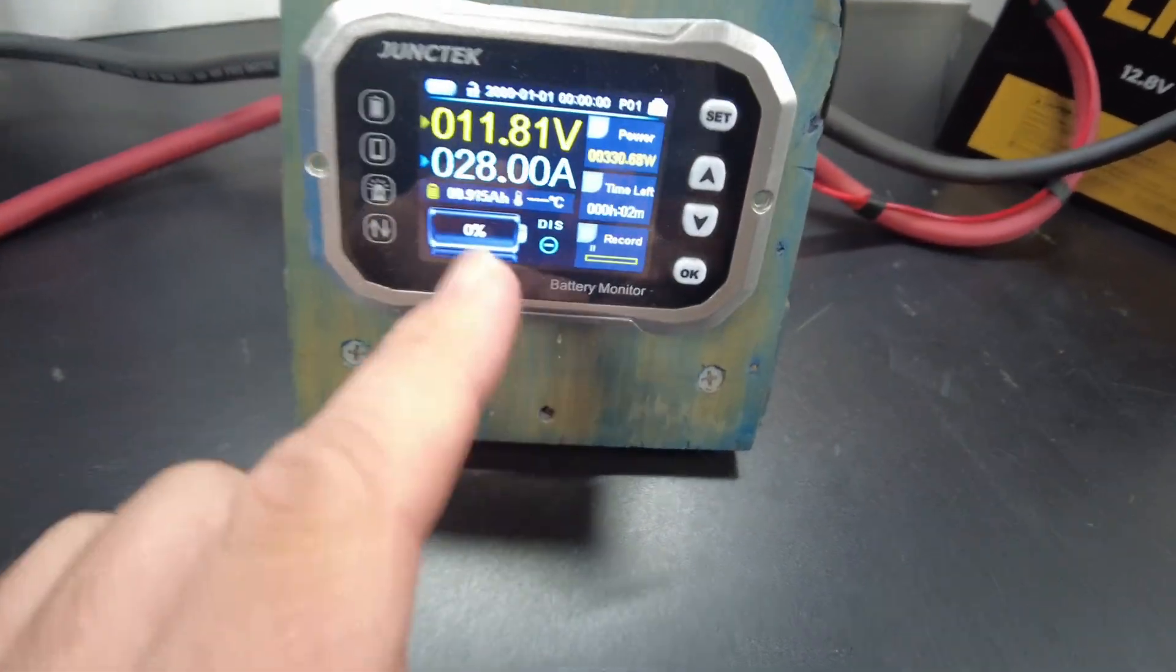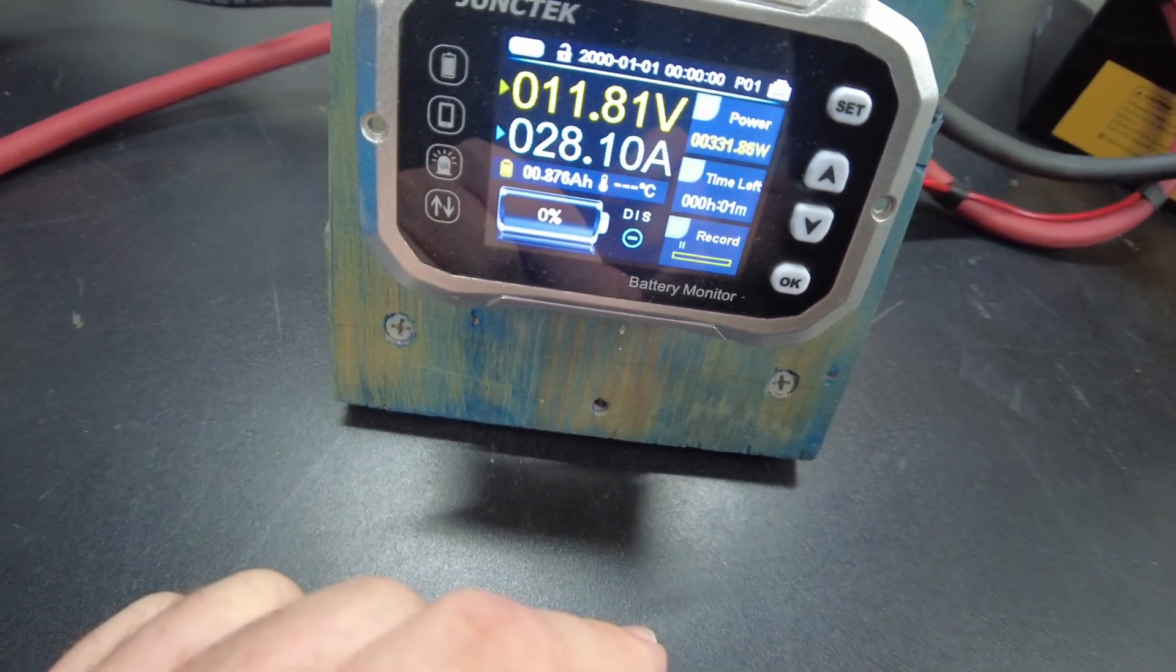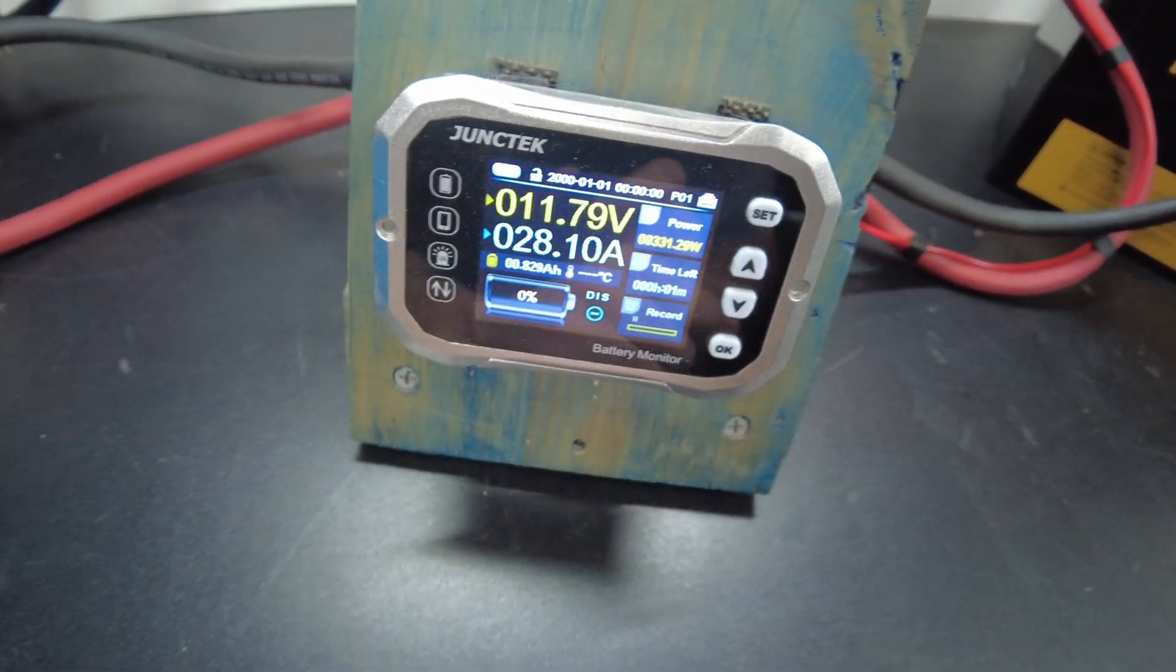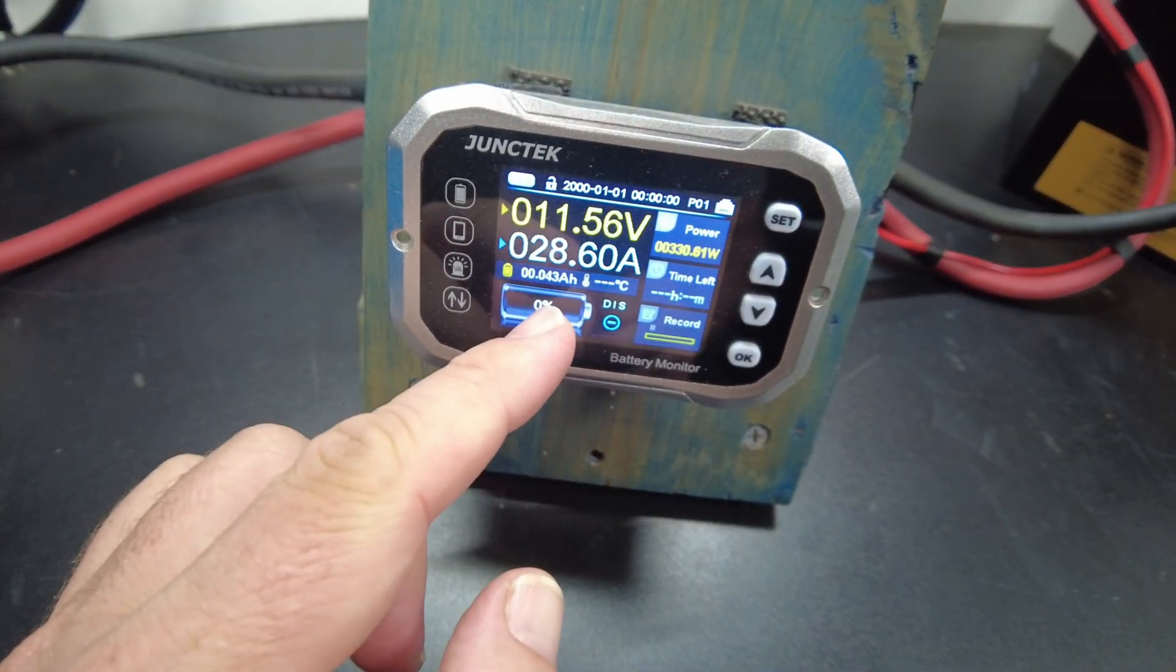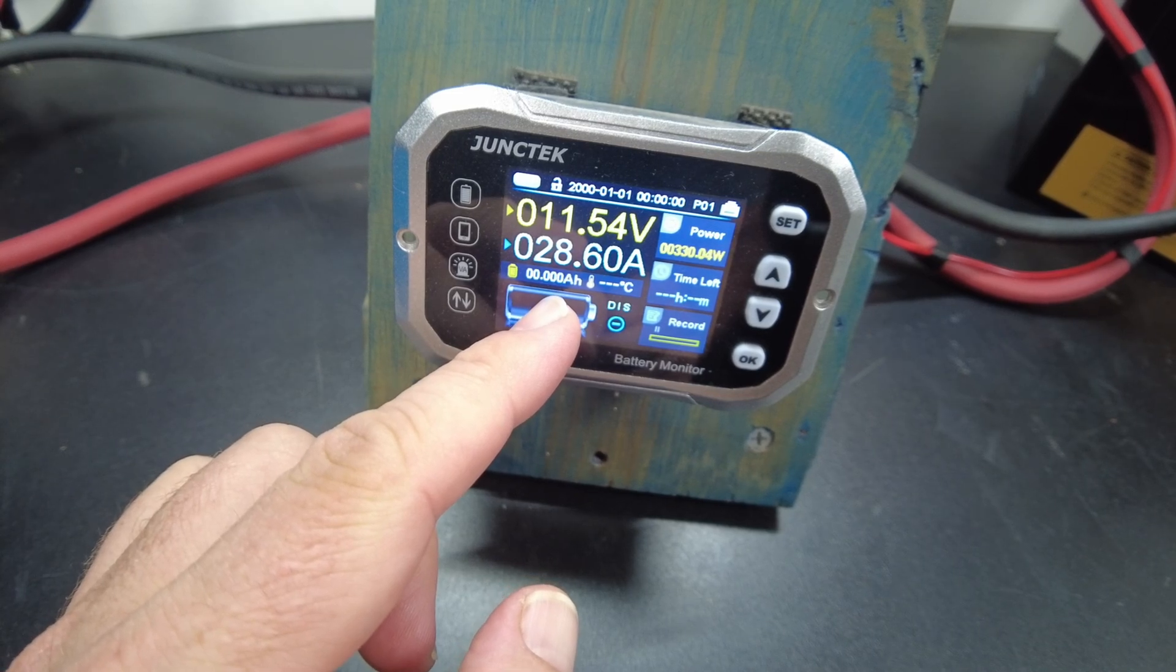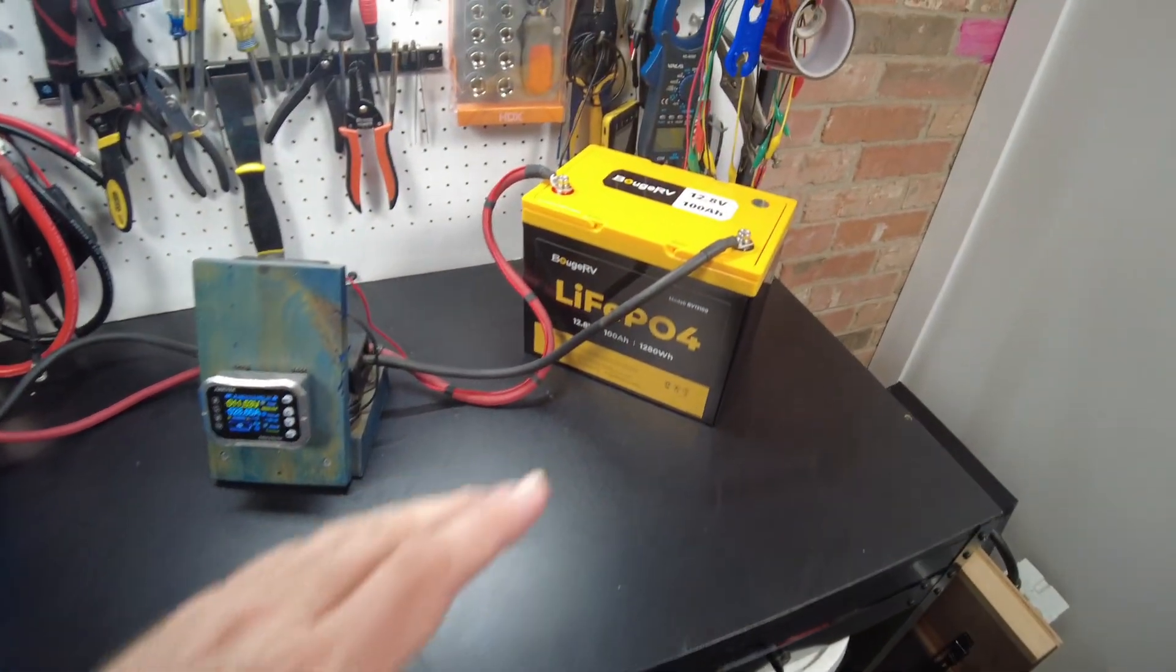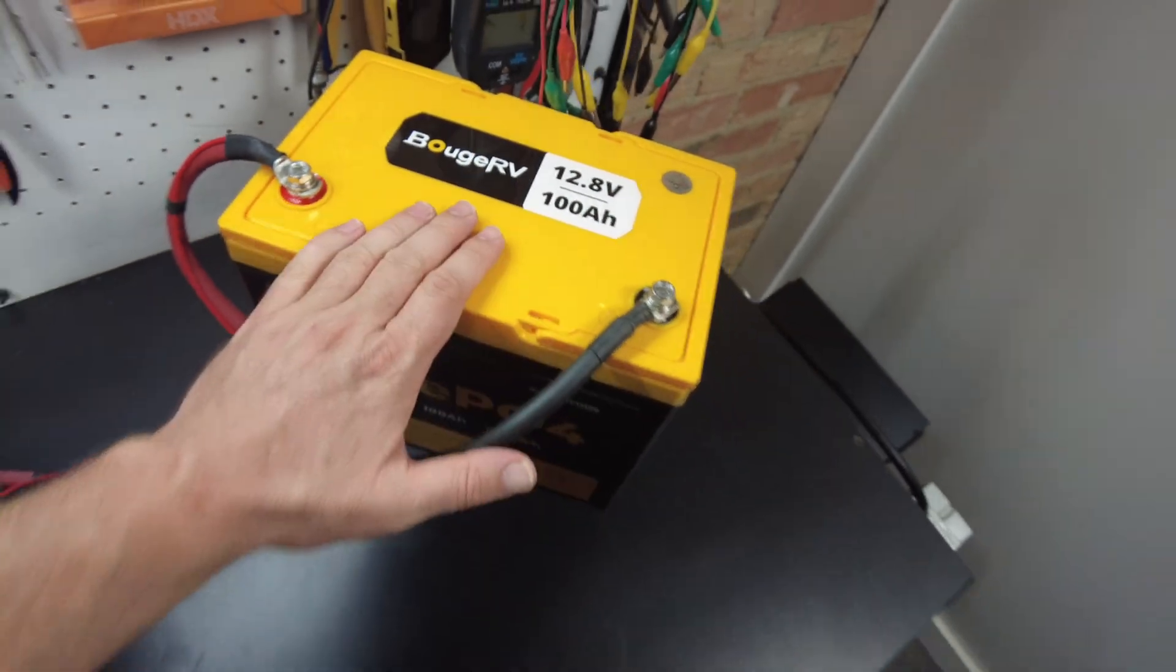Our shunt says zero. We still have about 0.8 amp hours left to go. So there's still a little bit in there. Here we go. We've got 0.02 and there we go. We have discharged the full 100 amp hours. So this battery lives up to its rating of 100 amp hours. It has passed.